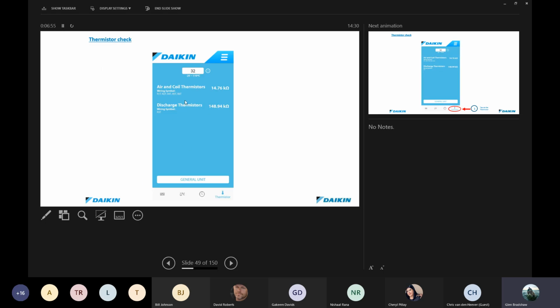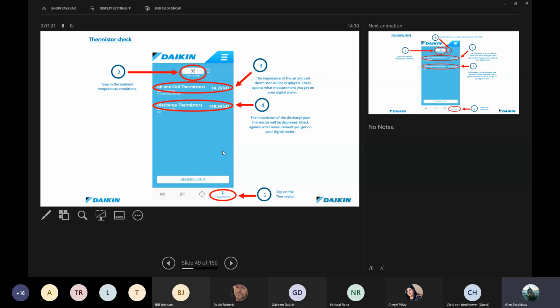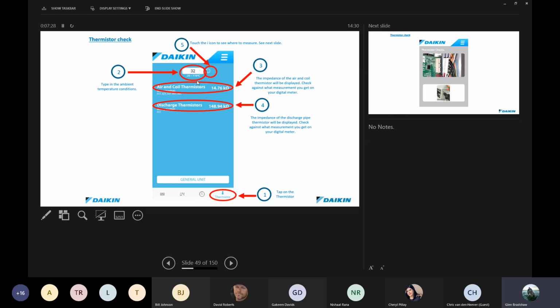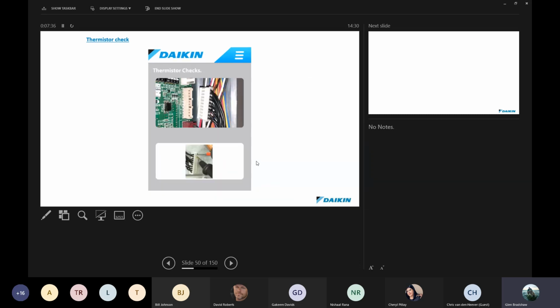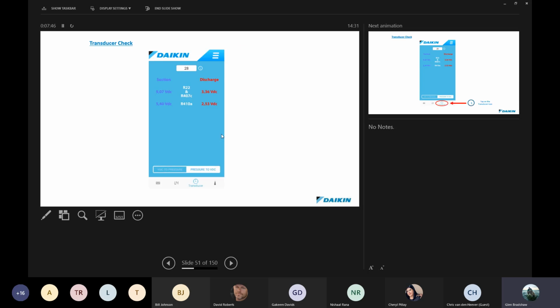The next part of the app allows you to also check thermistors. Here we've got thermistor. If we put in a temperature value over here, it'll tell us what the air and coil sensor resistance value is and what a discharge thermistor value would be. Remember, your discharge sensors above your compressor run on a different scale to the rest of the thermistors in a VRV unit. We covered a lot of this a couple of weeks back when we did the VRV advanced fault finding, and that recording is up as well. Very interesting, this little information button. If you tap on it, it helps you out. It will give you an idea of what the plug looks like and how to test it. There'll be little information things in there that help you drill down a bit further. Transducer check.